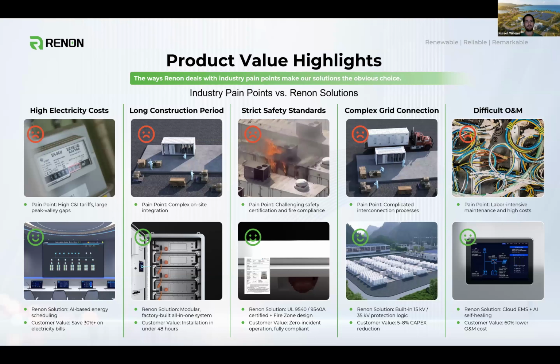Major highlights here: it's directly intended to save on the cost of electricity, even if you do it without solar. So even without any PV systems, it can provide value simply through energy arbitrage. A lot of the time you'll have peak charges in the 5 p.m. to 9 p.m. window, whereas energy is much cheaper from 1 a.m. to 5 a.m. That gives you flexibility to charge at night and discharge during the day when it's most expensive. Or even if you aren't looking to use this energy and you have a very low energy cost location, it can be used just as an investment structure by charging at the cheaper rate and discharging at the higher rate. It's a direct mechanism for energy arbitrage.